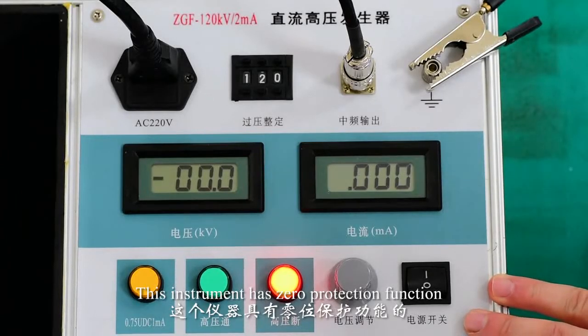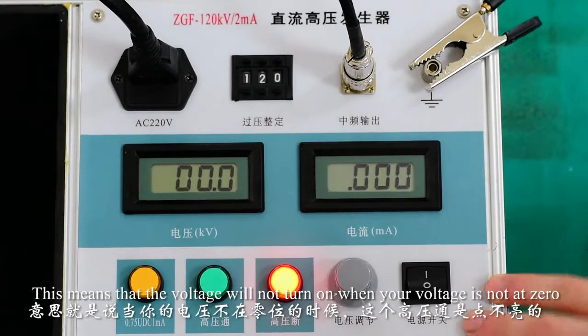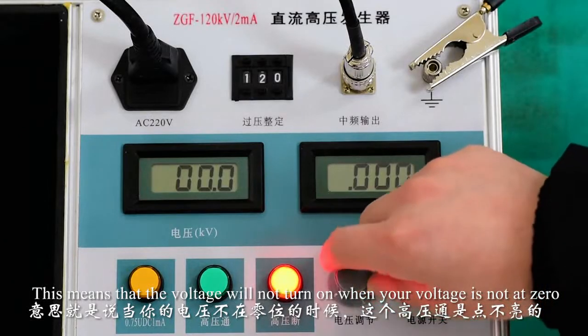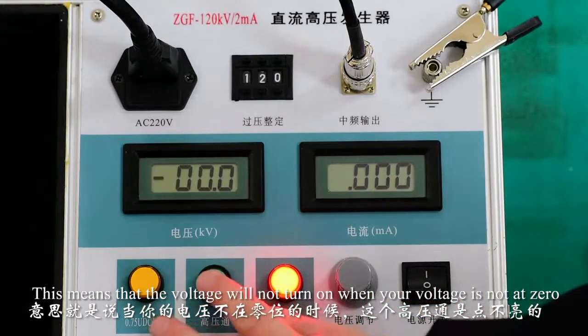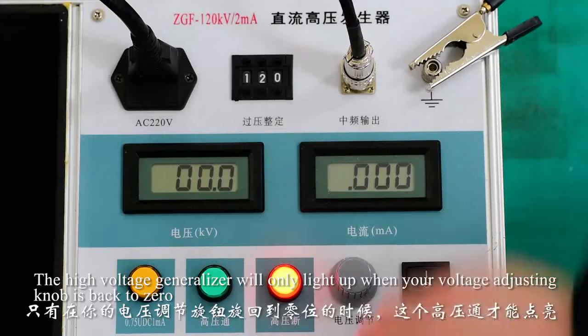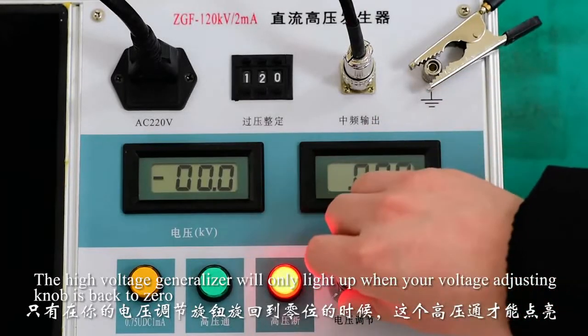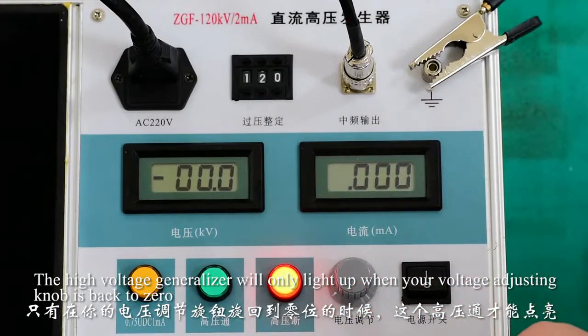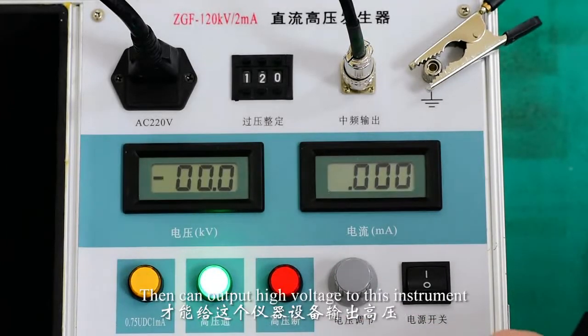This instrument has a zero protection function. This means that the high voltage will not turn on when your voltage is not at zero. The high voltage indicator will only light up when your voltage adjusting knob is back to zero. Then the instrument can output high voltage.